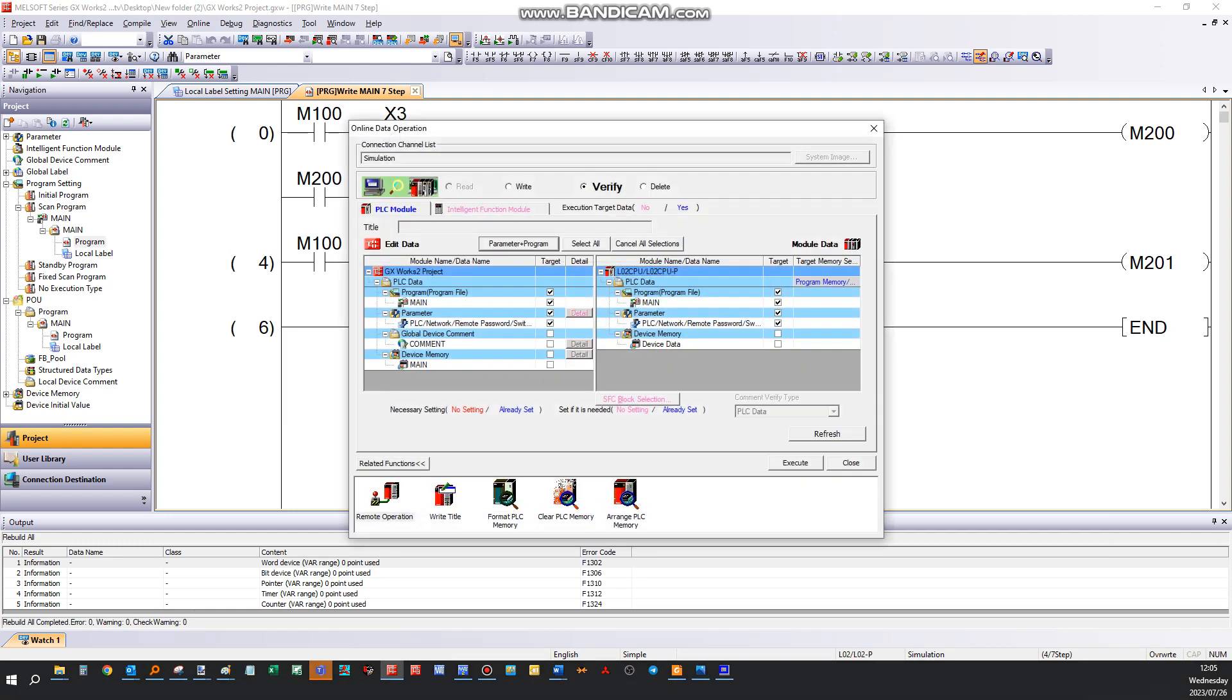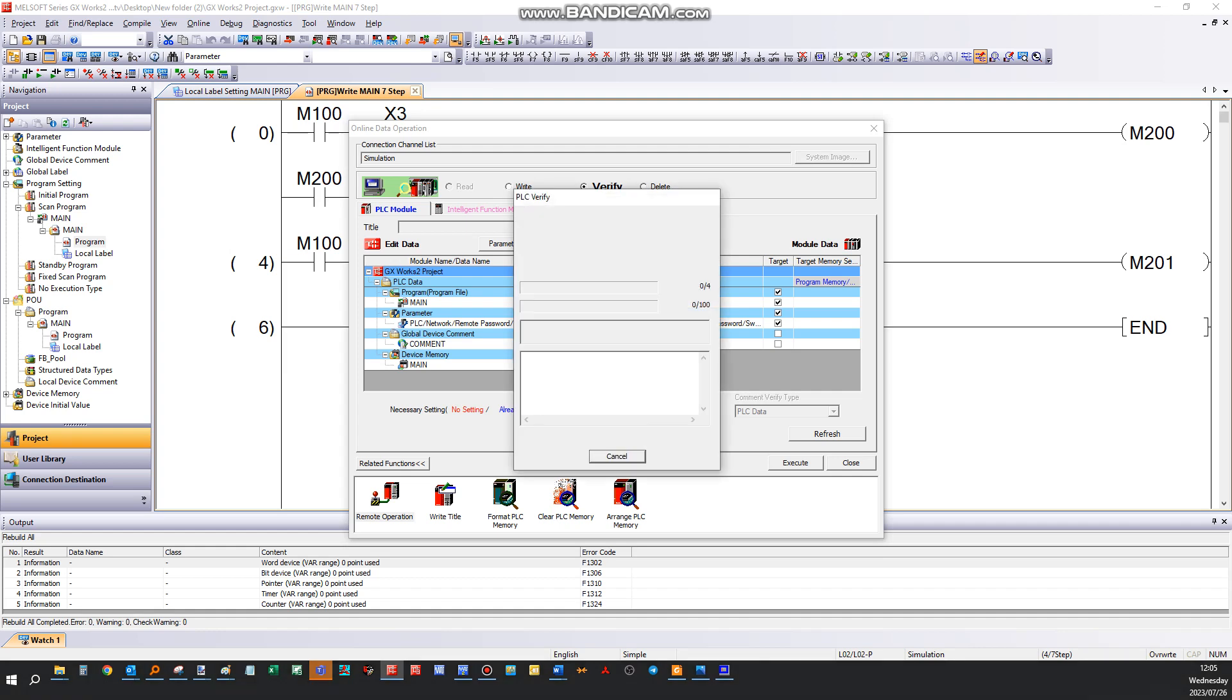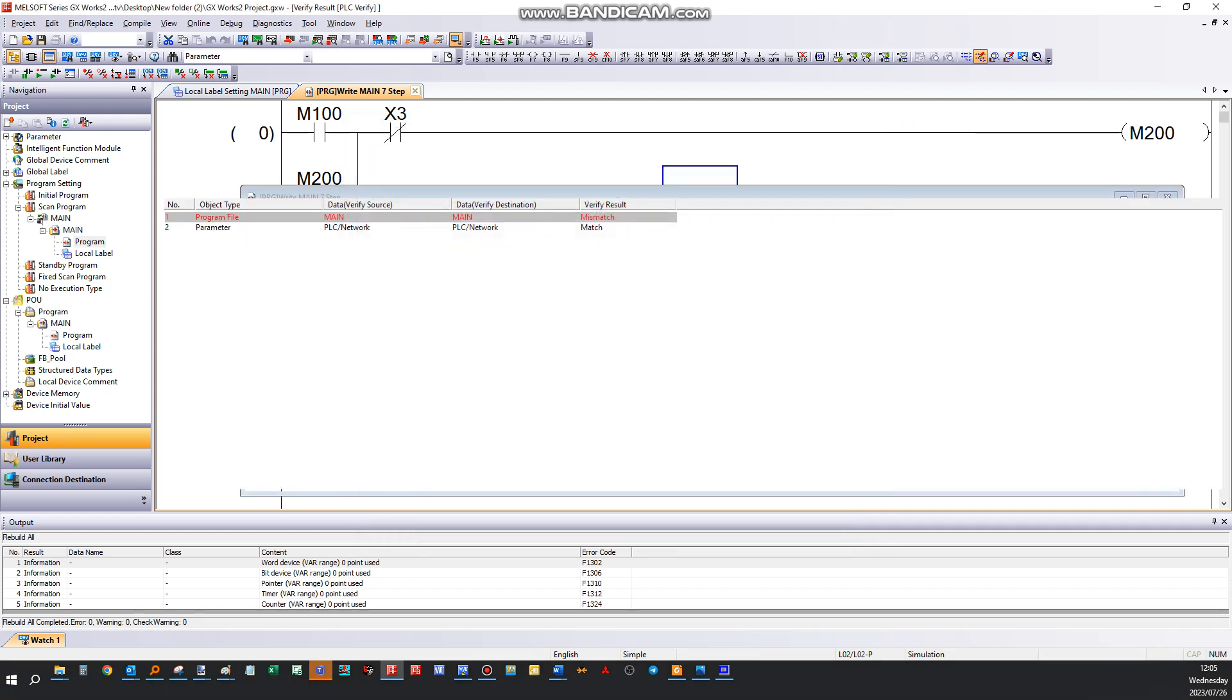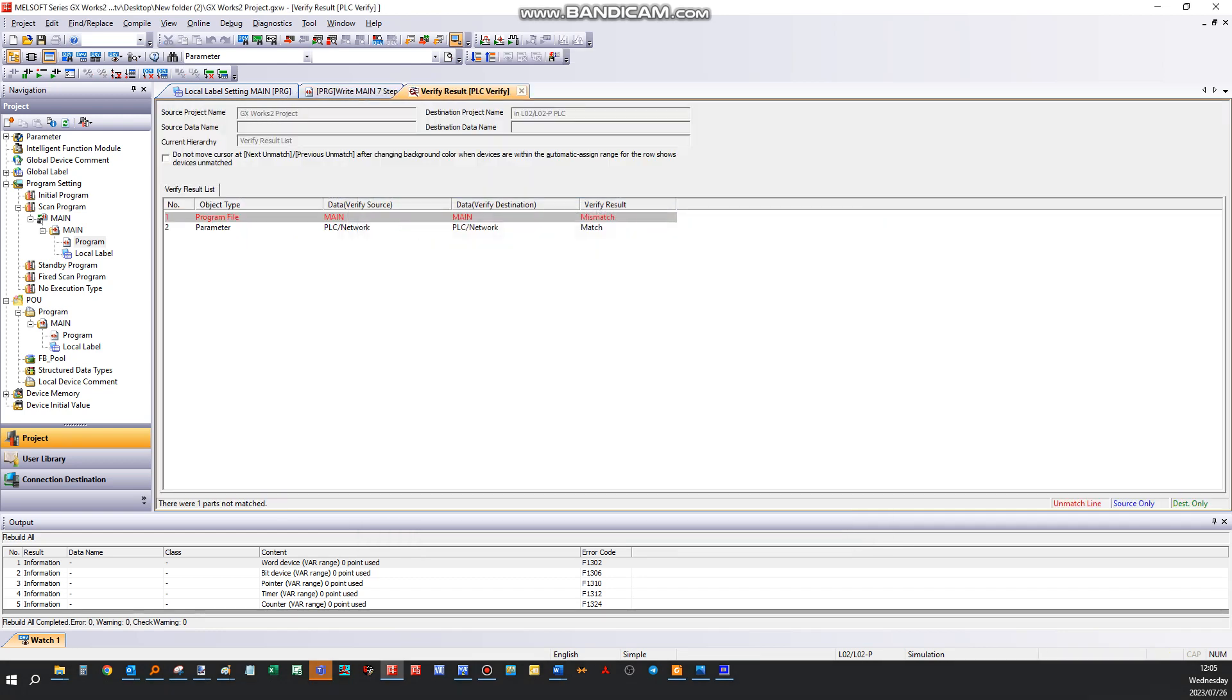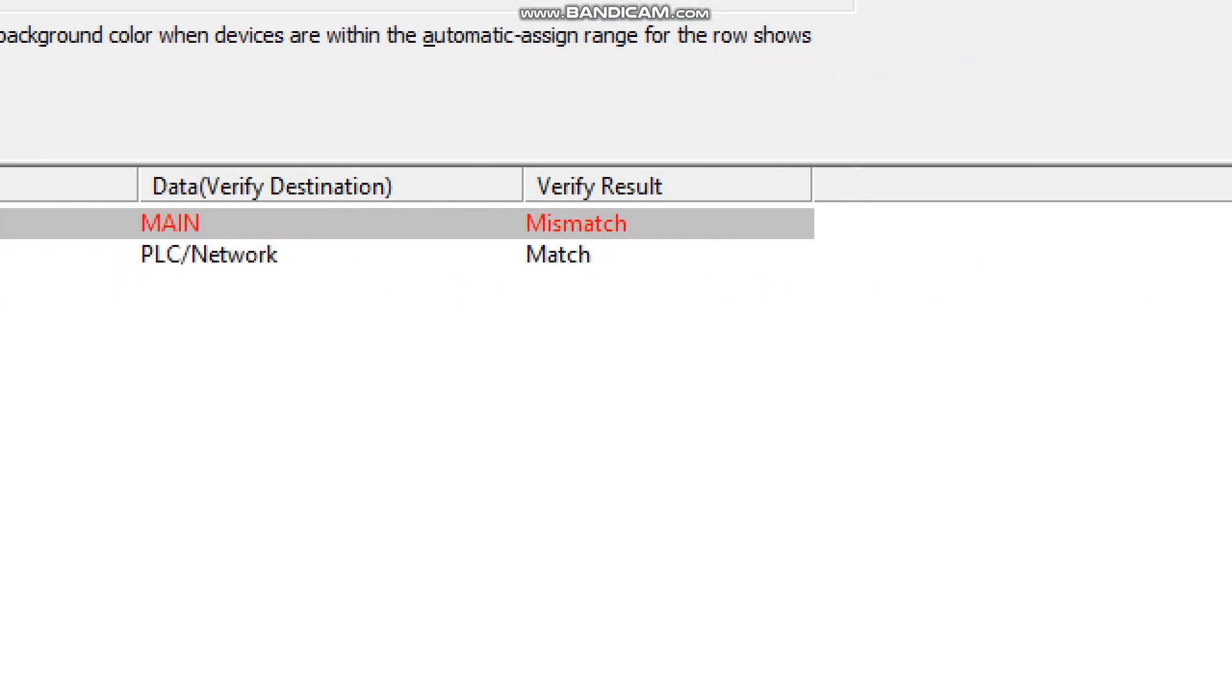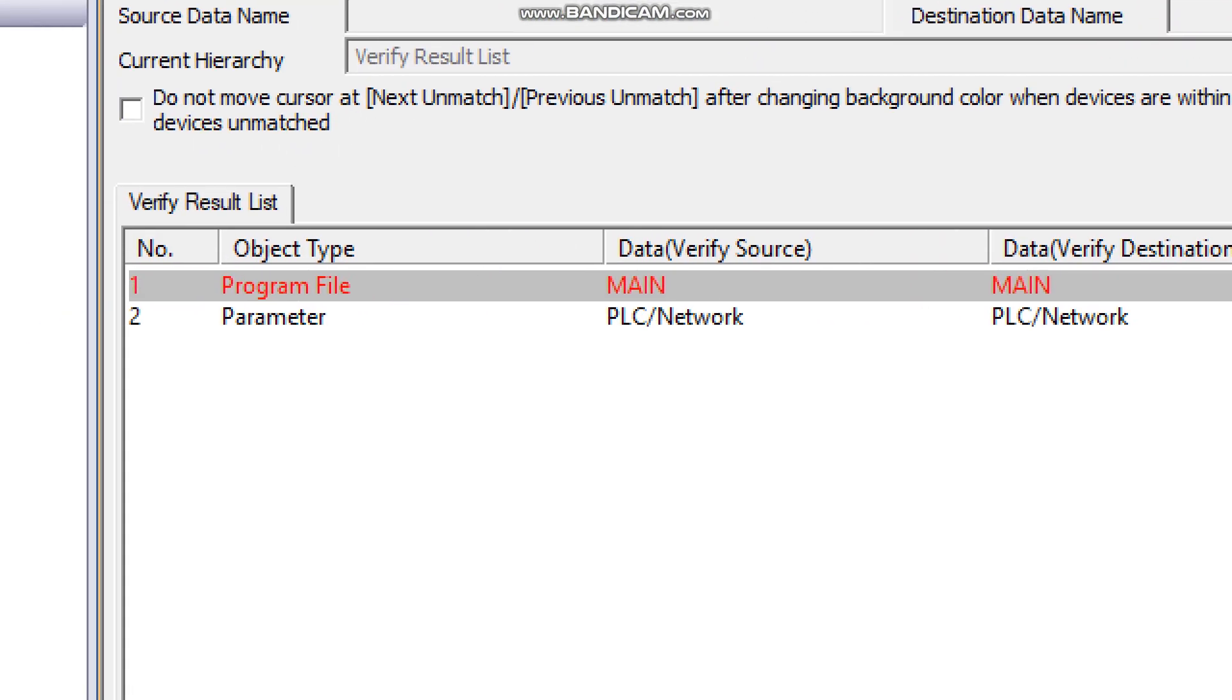We want to verify parameters and programs, execute. Now it will compare the program on your PC and the program on your PLC and compile that report. It will show you any differences. If it's black it means it's the same, if it's red there's differences, and the key below is where the differences are.